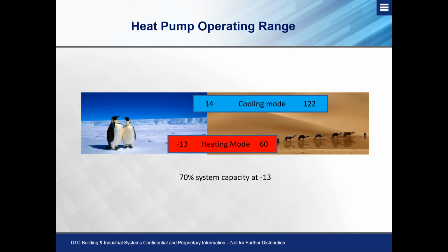capacity at -13. And again, just like the Carrier system that we were talking about prior, this all depends on the connected capacity and also the unit configuration, whether we're dealing with a single, dual, or triple module, coil surface area, and also the amount of compressors that we're dealing with for that low ambient heating capacity. But as a rule of thumb, like I stated before, if we look at a 6-ton system, it will give you 70% of that system's rated capacity at -13 and just about 100% at 5 degrees. But again, it all varies on the type and configuration of equipment that you have.